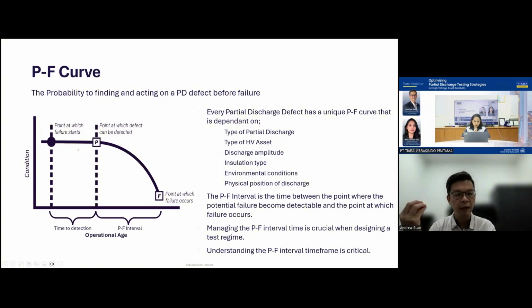Then you try to know which type of HV asset it is on. Is it on my cable, my switchgear, or my transformer? Then you may want to go even deeper. Which part of the transformer? Is it inside the oil tank, or inside the cable termination? This will also determine how fast or how short the P to F interval is. So that is the type of asset.